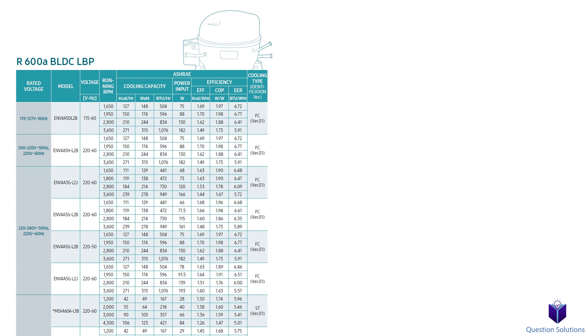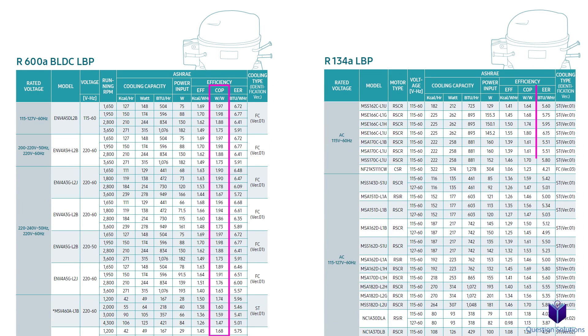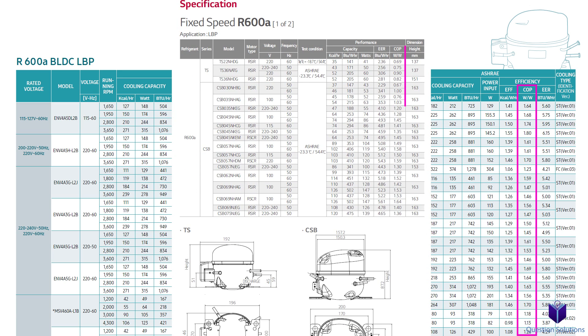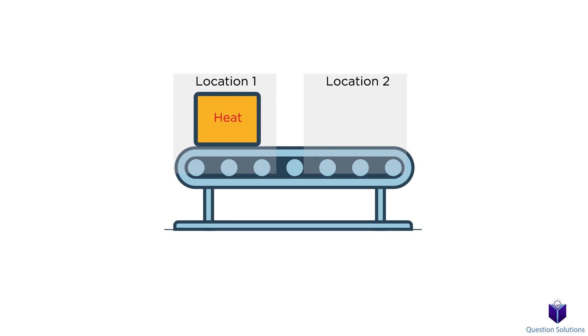Keep in mind that COP values can be greater than 1. In simple terms, the amount of heat removed from the refrigerator space can be greater than the amount of work input. We're moving heat from one location to another, and to move that heat requires some energy. The keyword being 'move.' This is why COP values can be greater than 1, because a small amount of work can move a large amount of heat.